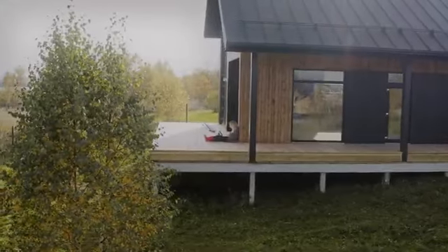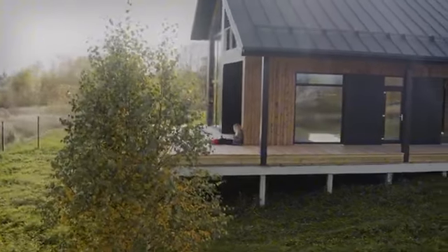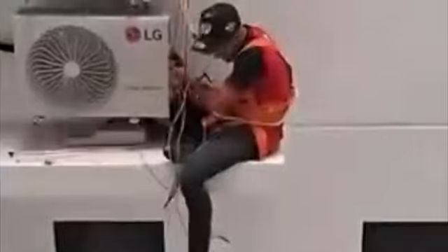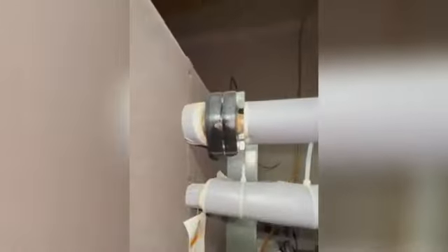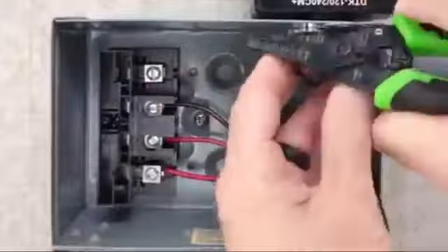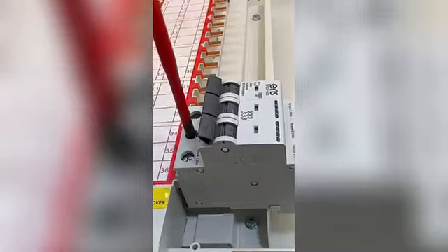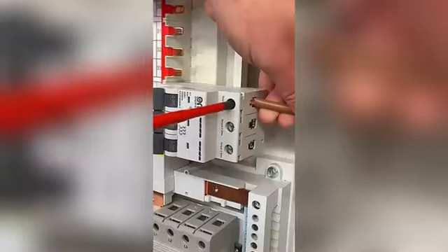This is the protocol for every homeowner in a house built after 2005. 2. Commission the refrigerant charge. Hire an HVAC technician with manifold gauges and a scale. Verify superheat and subcooling match manufacturer specifications. $150 to $250. This adds 8 to 12 years of compressor life. 3. Install a surge protector on the outdoor unit. Lightning strikes and grid fluctuations destroy control boards and compressors. A whole unit surge protector costs $200 to $400 installed. One surge event costs $1,500 to $3,000 in damage.